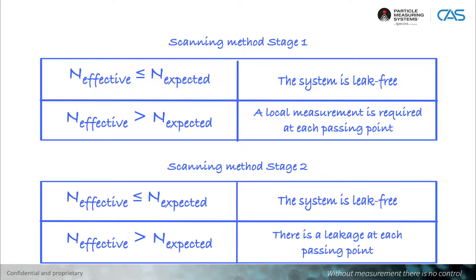If, at stage 1, the effective number of particles exceeds the expected number of particles, local leak verification is required at each position. While in stage 2, there is a leak from the filter system every time the effective number of particles is exceeded.